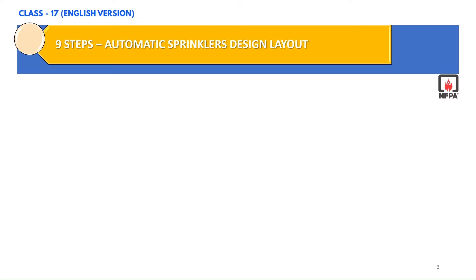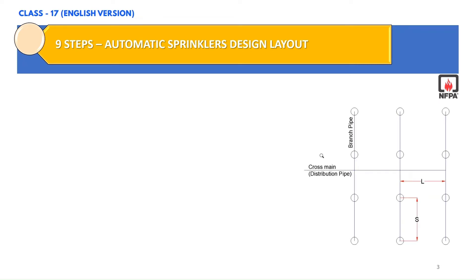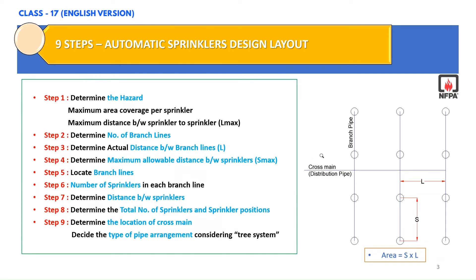Before we move forward with the 9-step formula, let us have a look at the screen. S represents the distance between sprinkler to sprinkler, and L represents the distance between branch lines. The area covered by one sprinkler is calculated using the formula: Area A equals S multiplied by L. Let us now have a look at the 9-step formula that is mandatory to place the sprinklers on any layout.